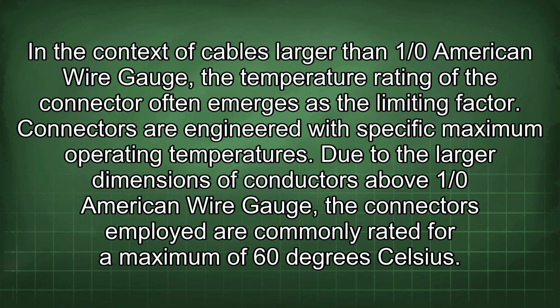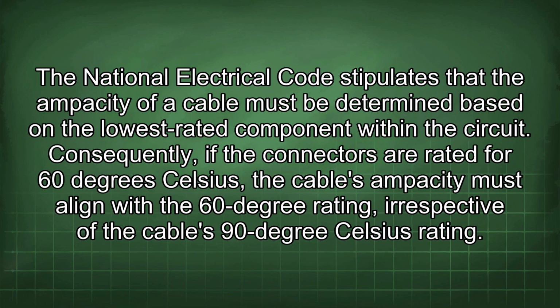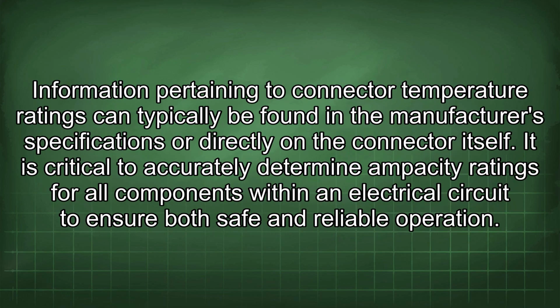Connectors are engineered with specific maximum operating temperatures. Due to the larger dimensions of conductors above 1/0 American wire gauge, the connectors employed are commonly rated for a maximum of 60 degrees Celsius. The National Electrical Code stipulates that the ampacity of a cable must be determined based on the lowest rated component within the circuit. Consequently, if the connectors are rated for 60 degrees Celsius, the cable's ampacity must align with the 60-degree rating, irrespective of the cable's 90 degrees Celsius rating. Information pertaining to connector temperature ratings can typically be found in the manufacturer's specifications or directly on the connector itself.